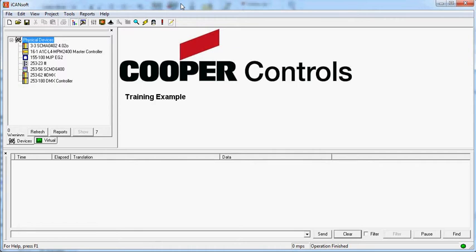The first thing we need to do is have installed the drivers for the touchscreen. Best to start this by connecting your computer to the touchscreen using a USB A to B cable. When Windows asks for the drivers, they're located in the normal position. In your program files, your Cooper controls directory, go to iCANsoft and there's a USB directory.